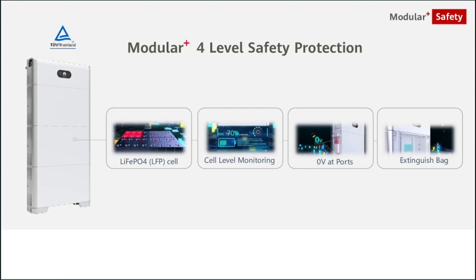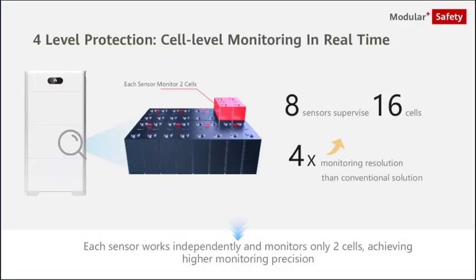The next step, second level, is our battery management and cell monitoring, which we equip on each pack - I'll come into detail on the next slides. The next safety level is our 0-volt protection on each touchable port of the battery, similar to what we provide on the rooftop with our optimizers on the PV modules. The same applies to the battery modules - we can shut them down to 0 volt. And last but not least, level 4, we add an extinguish bag on each battery module. I'll explain what this means in detail on the next slides.